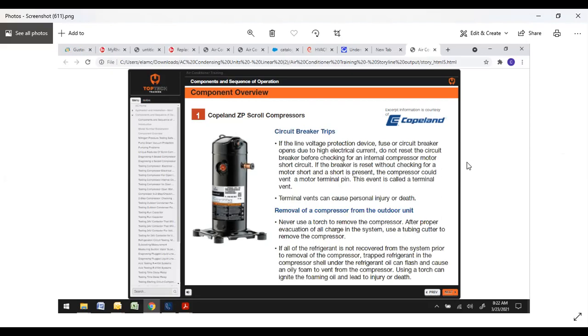This is a big one here. This goes for Copeland and pretty much any compressor. Circuit breaker trips. If you come across a unit that has a circuit breaker tripped, and you reset it and it trips again, don't keep resetting it. There's a reason that it's tripping. So at that point, you'll want to start checking to see what could be shorted. If the breaker is reset without checking for a motor short continually and a short is present, the compressor can vent a motor terminal pin. This is called a terminal vent.